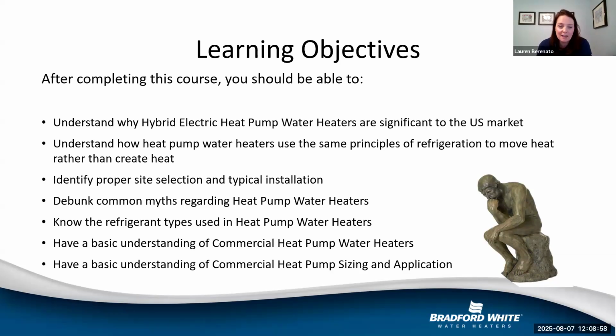So I will say here in the beginning, the challenge with heat pump sizing and application commercially is no manufacturer has a sizing software on their website for you to size. Everything is based off of the engineer or designer utilizing their own guidelines to develop the best process, I should say, for sizing their heat pump on their own using the math calculations from ASPE as well as ASHRAE guidelines. So you're really going to have to hone in on the installation manual that is present when you're specifying your product.